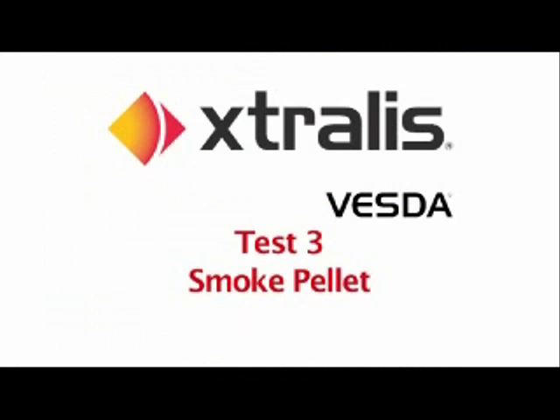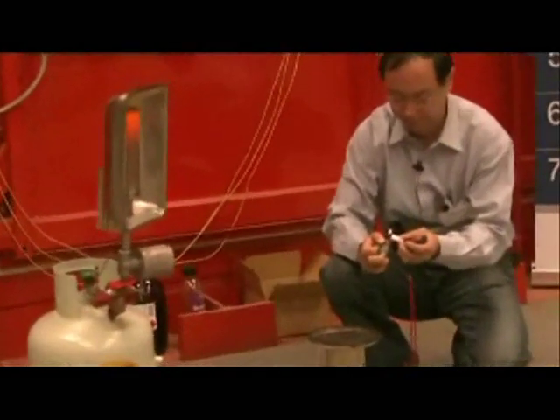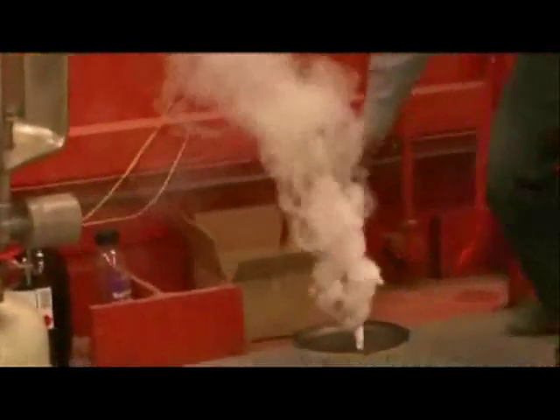Smoke pellet. Test number three is conducted to AS standards and consists of a small three-gram smoke pellet, assisted by a radiant heater to provide a constant heat release rate. The VESDA unit went into alert after just seventy-two seconds and fire one after ninety seconds. Both the spot detector and beam detector failed to react within the eight-minute period.